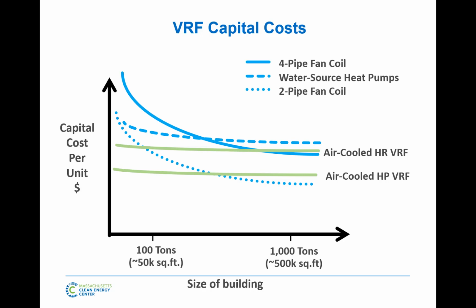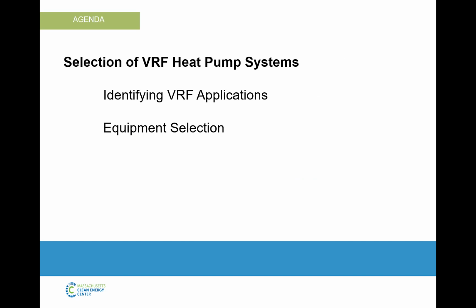Typically, I'd say this kind of answers what VRF's sweet spot is. Definitely any building 100,000 square feet and under, VRF is going to be well within that sweet spot. Doing a building 100 to 200,000 square feet is not unheard of in this area, and it definitely shifts based on building design and what other benefits you're getting out of the system. If you're looking at a 500,000 or a million square foot building, typically the 4-pipe, 2-pipe fan coils right now are going to have a greater cost advantage when you look at how that system's set up on a per unit basis. The question was, do we ever get asked or see data for a cost per ton?